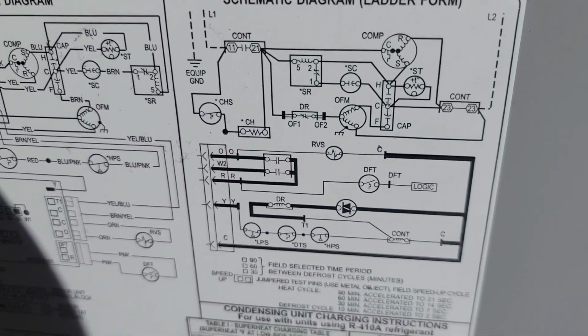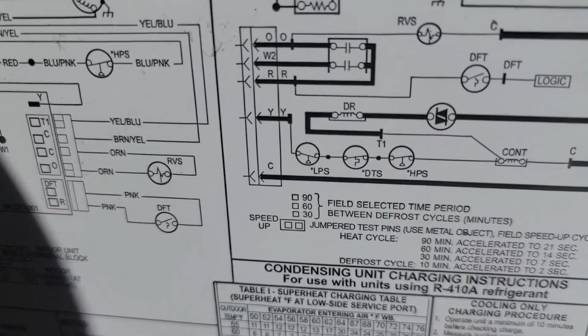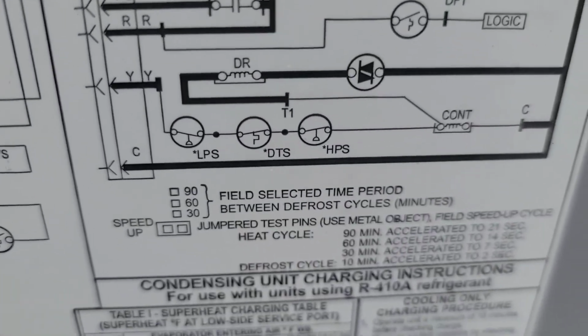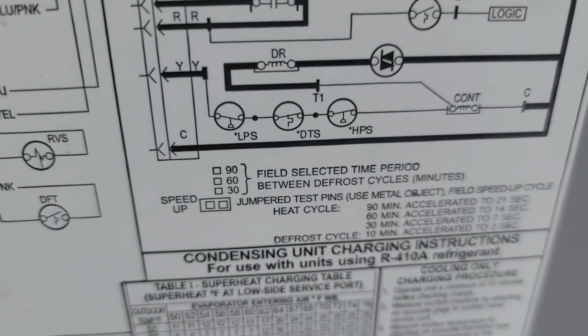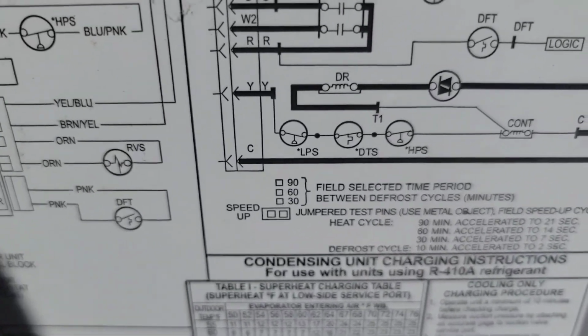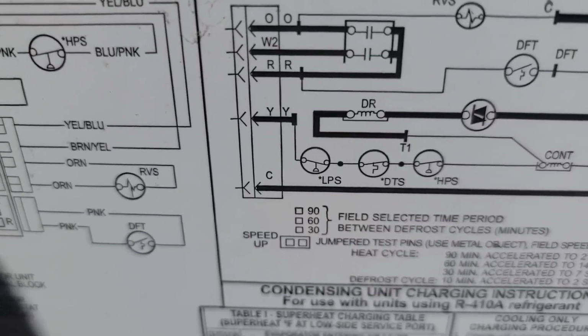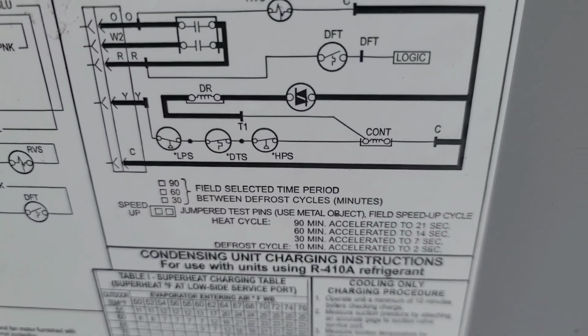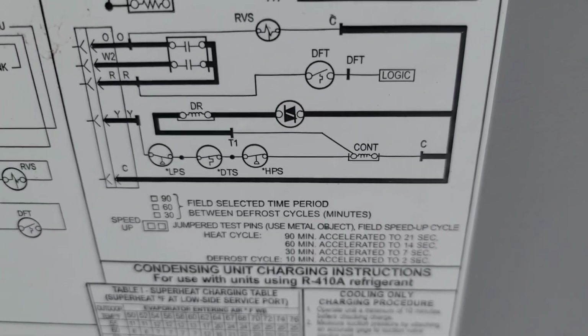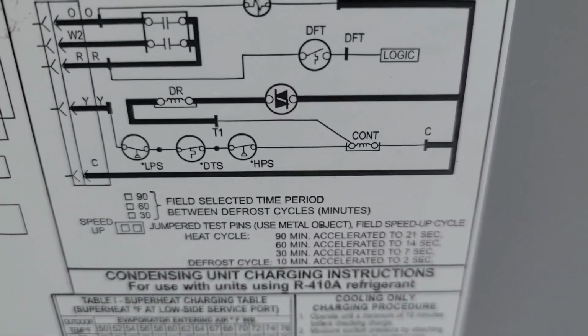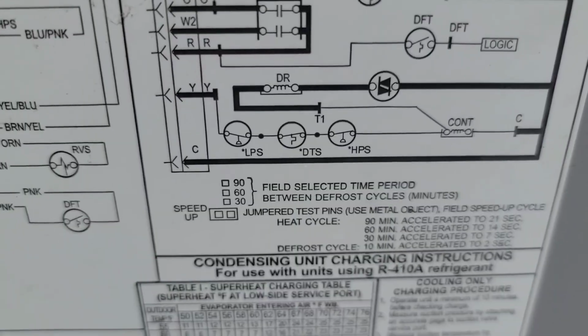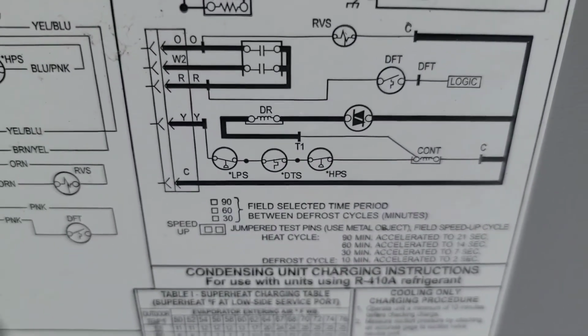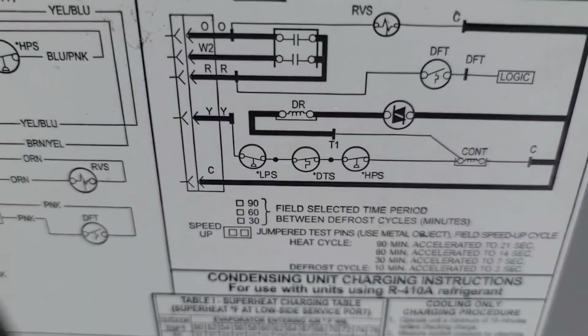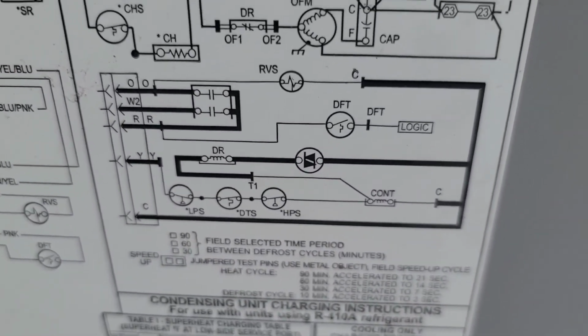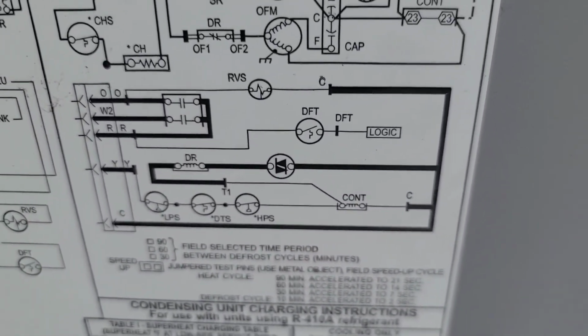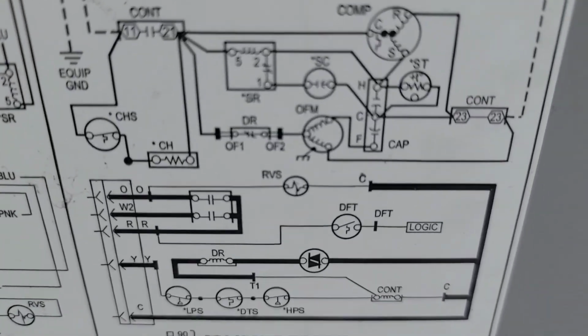If you don't know how to read schematics, you need to learn. There's the low pressure switch, that's the defrost temperature switch, and the high pressure switch. They're all in series with the call for Y. That low voltage wiring goes to one side of the contactor coil. See that? C-O-N-T, that means contactor coil. We got a common and a yellow, and that's what energizes that coil. And then we've got a defrost relay. Right there's the coil of the defrost relay. Defrost thermostat. So, pretty simple.